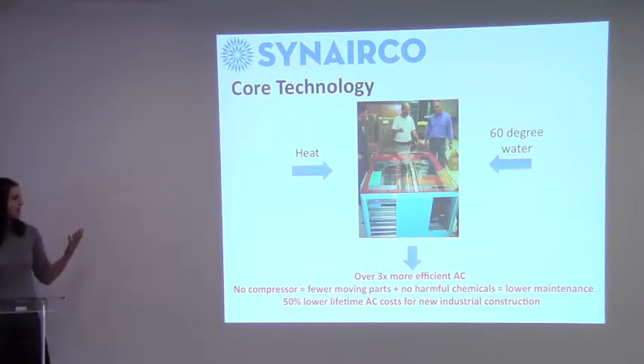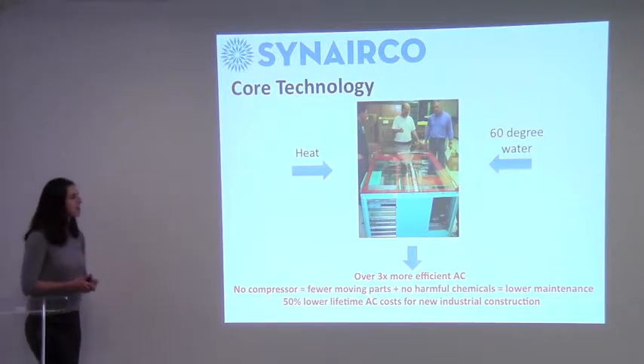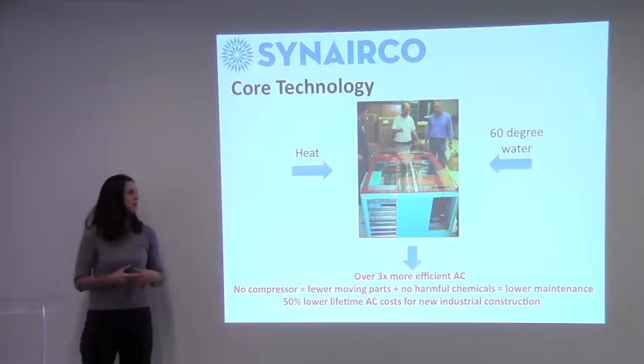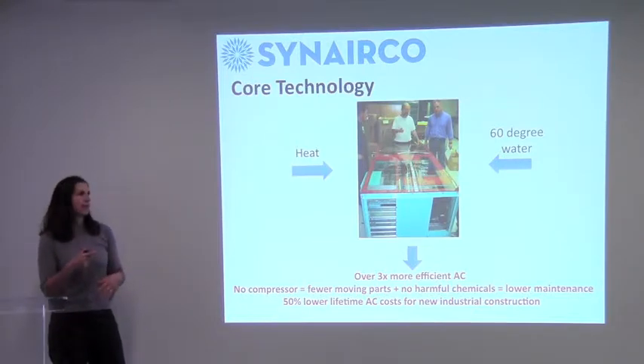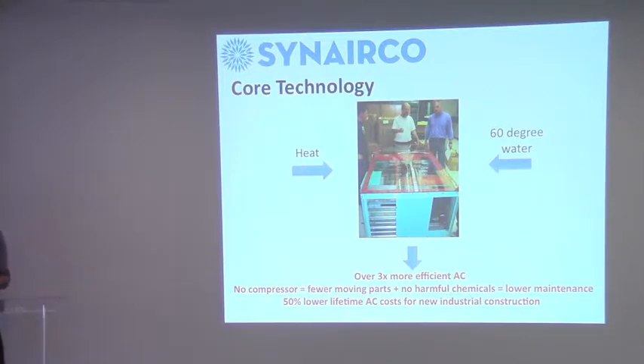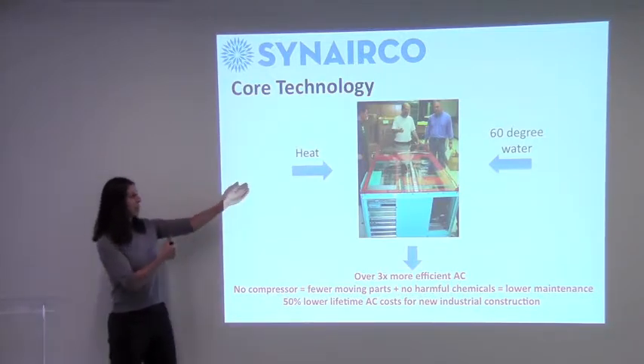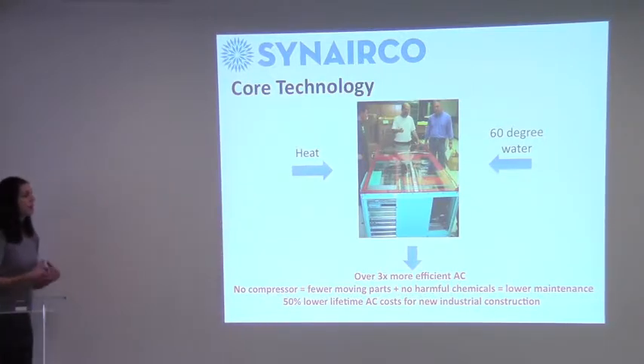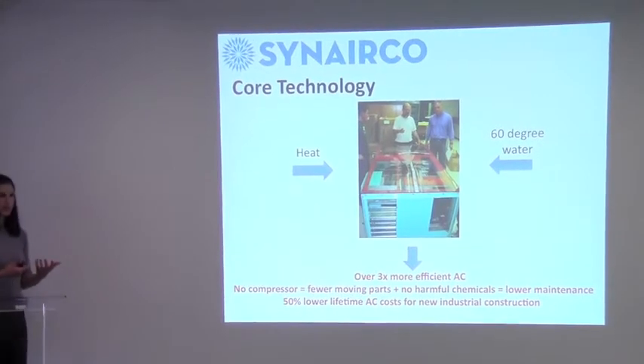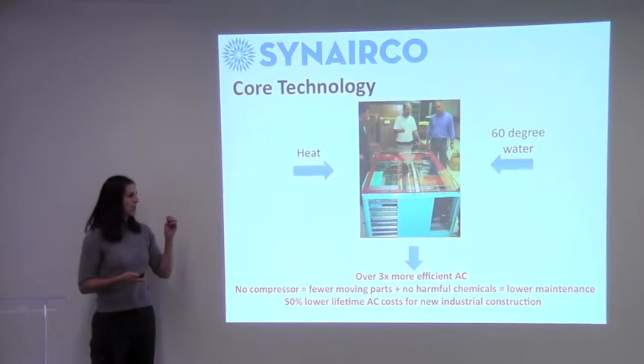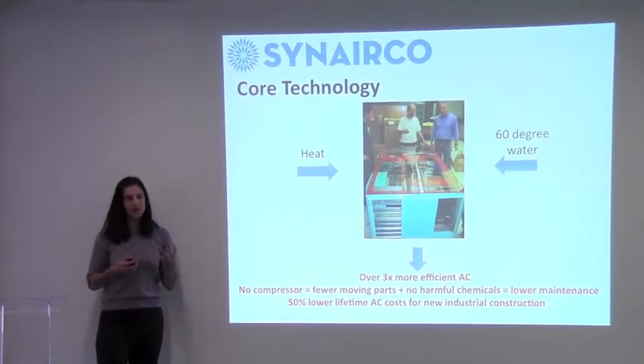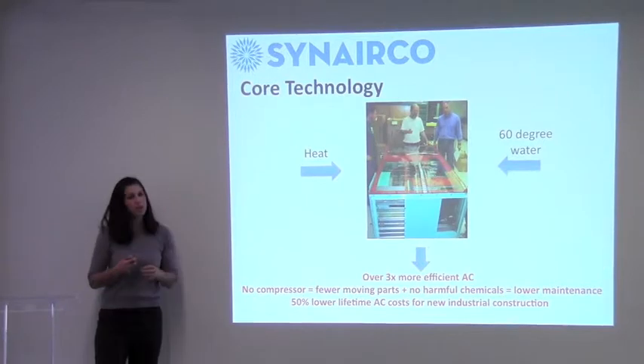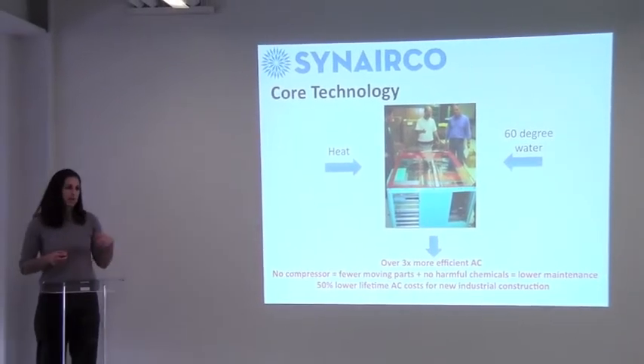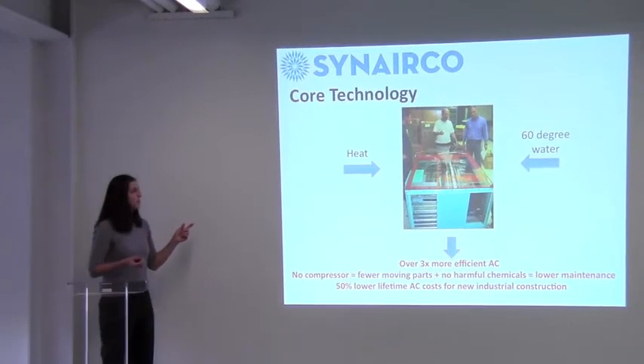Like I said, out of the box it performed better than we expected. We had predicted a COP of around 1.2, because we thought it would be twice as efficient as traditional absorption technology, which is around 0.6 — we're a heat-fired technology, that's why we compare to absorption. Well, out of the box we achieved a 1.8 COP. Those calculations used data from the lab, where we used a chiller to simulate groundwater and an electric heater to simulate a free source of heat.